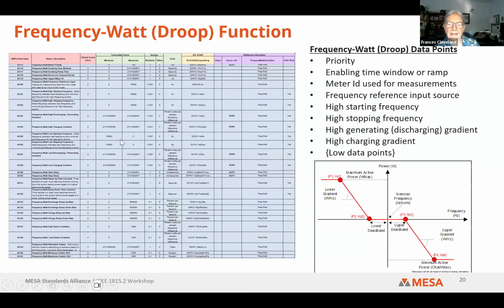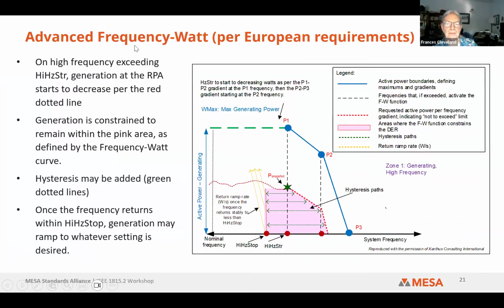So we have, as an example here, what we've called advanced frequency watt, which meets the European requirements rather than the droop requirements that are in 1547. So these are some functions that could be used, again, with the frequency watt capabilities, so that you can have more than just droop. You can have managing where exactly the function applies, where it doesn't, how it ramps back up to normal situations. So there's a lot of power to these functions.